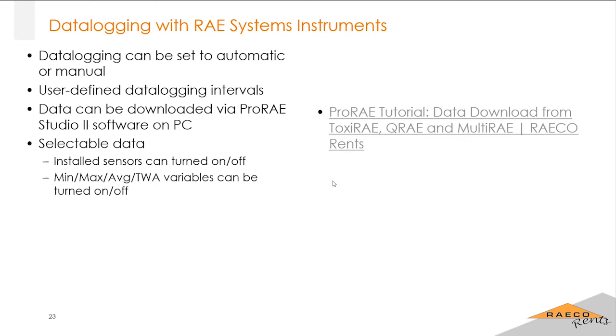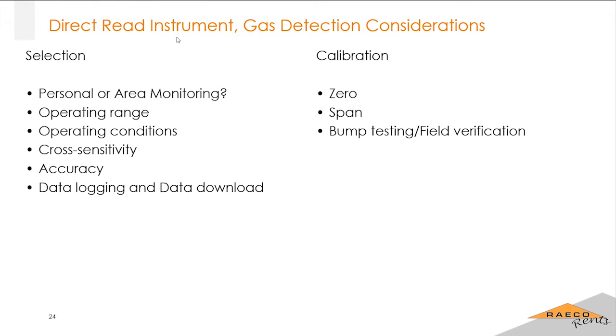Okay, good. All right, so with these direct reading gas instruments, a few things to think about, which I kind of mentioned earlier: are we doing personal or area monitoring? What is the range of the measurements? Is the instrument sensors going to be within that range? It doesn't happen very often, but every once in a while, someone will rent something and then they realize that their readings are well out of the range of the sensor. So just always keep that in mind.